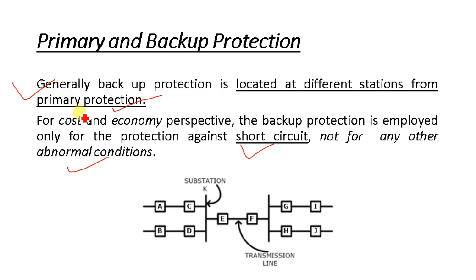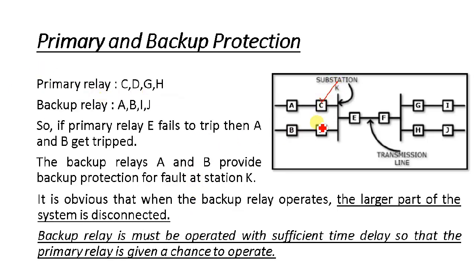Now let us understand the concept of backup relaying applied to a transmission line. We have a transmission line with protection at sections E and F, and a substation at point K. In this diagram, relays C, D, G, and H are primary relays, while relays A, B, I, and J are backup relays. If our primary relay E fails to trip when there is a fault, the backup relays A and B should get tripped.